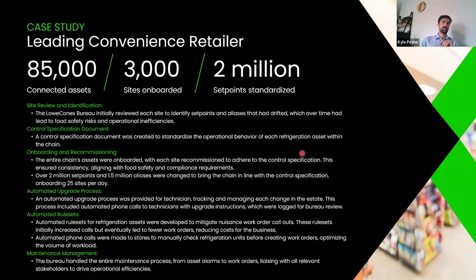Yeah, it was good. The set point standard - we run into it all the time, especially during initial installation and commissioning, where if there isn't tight control, things get done on site to get the system over the hump, get it operational, meet a deadline, and a set point or system parameter change is made that shouldn't be made. It has long-term effects, and we've seen that happen often.